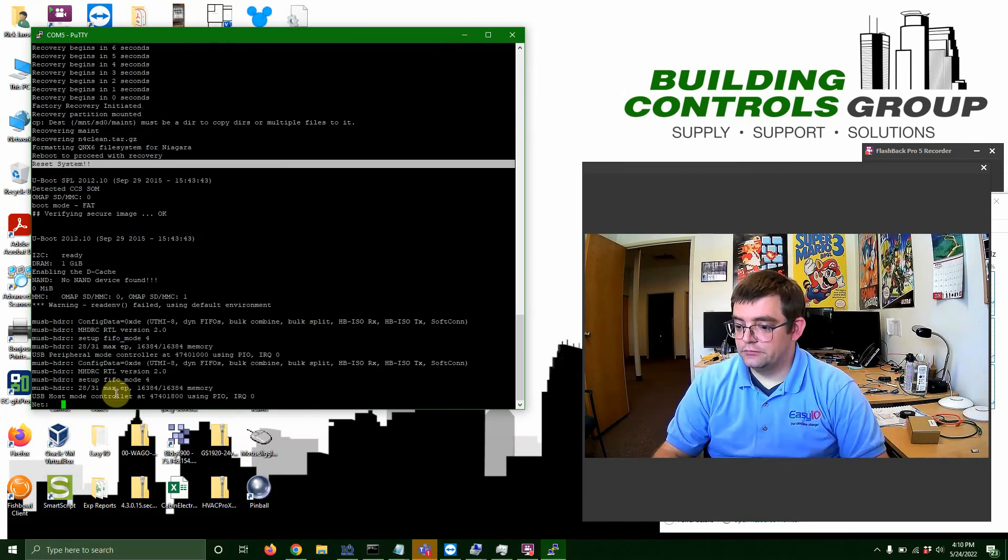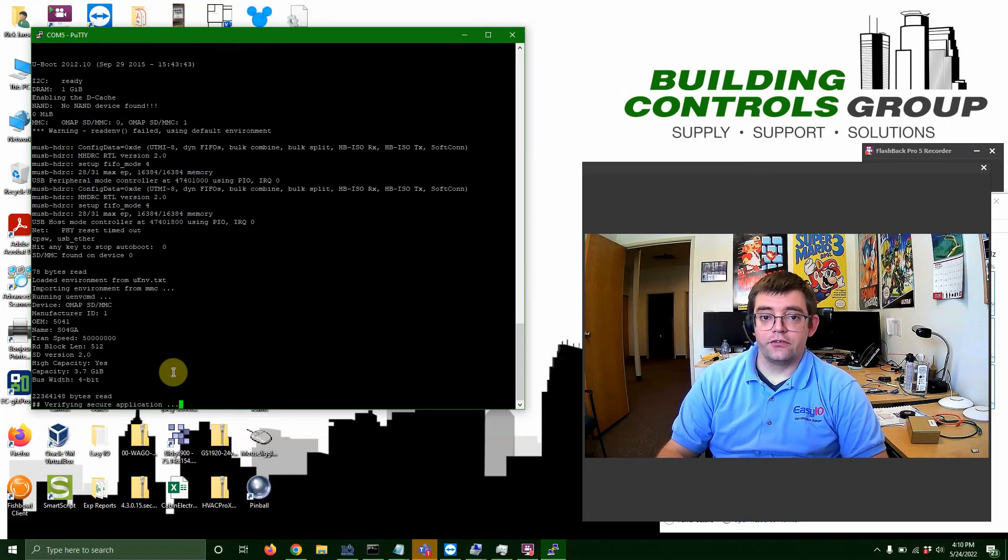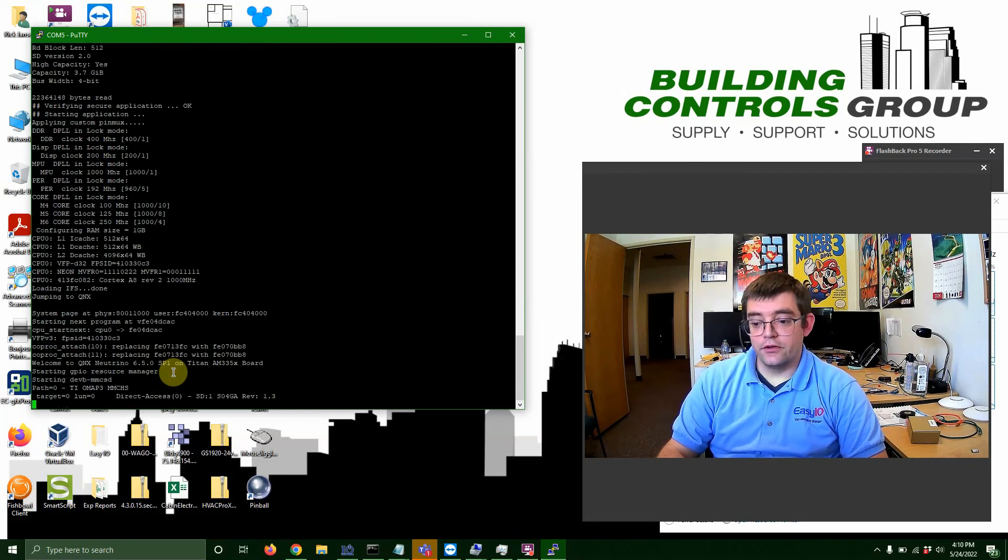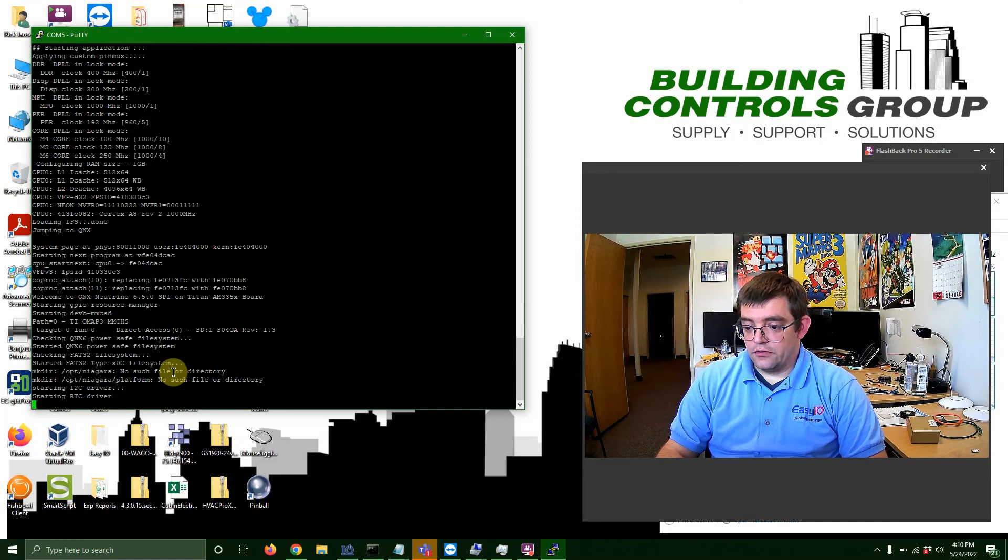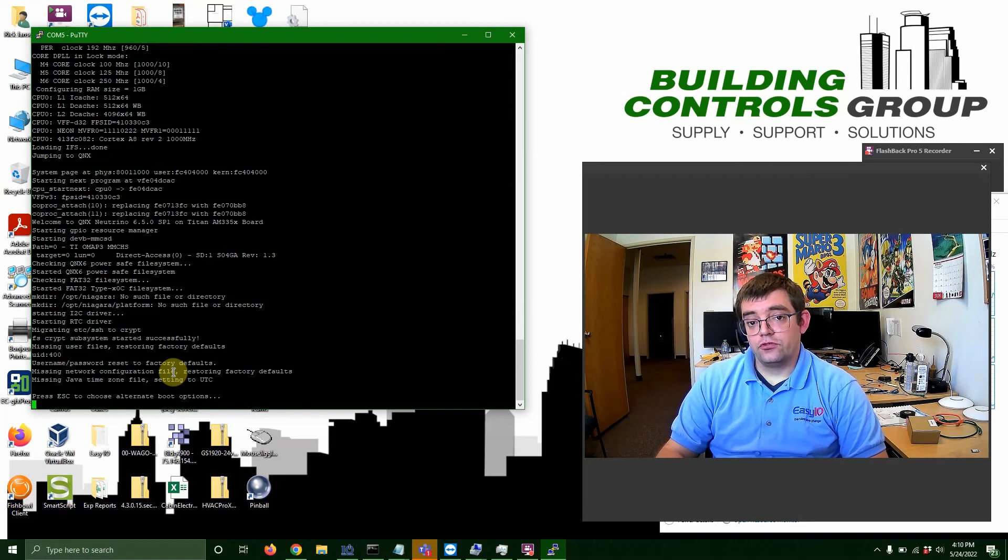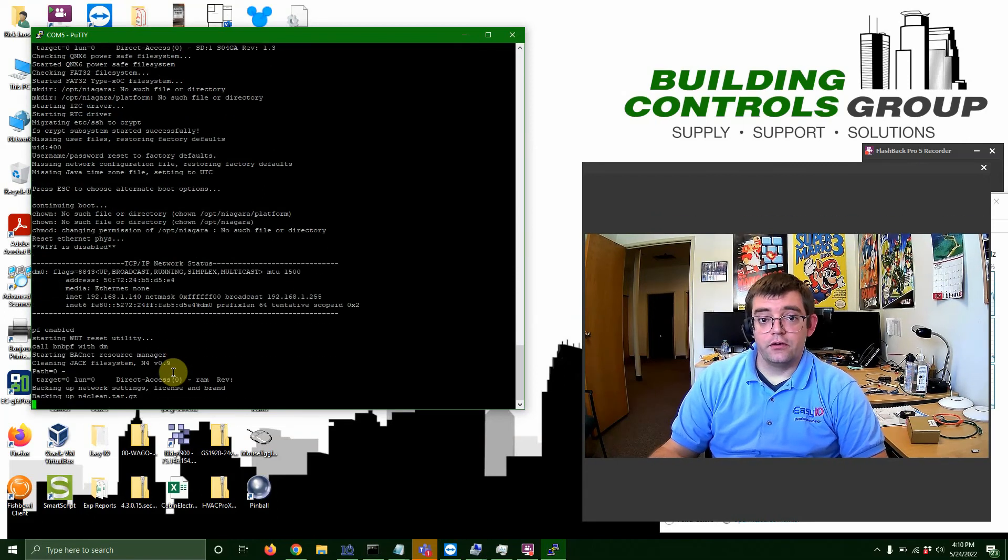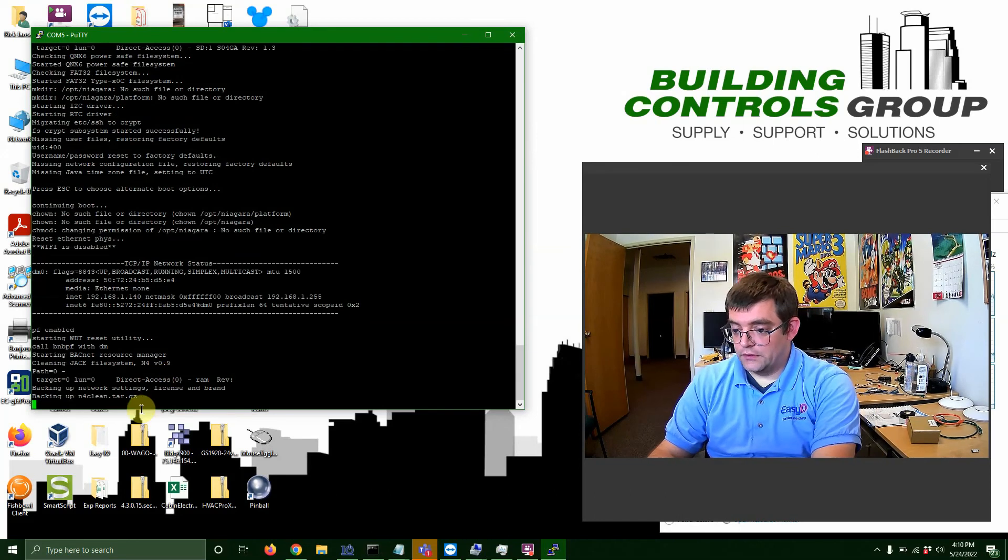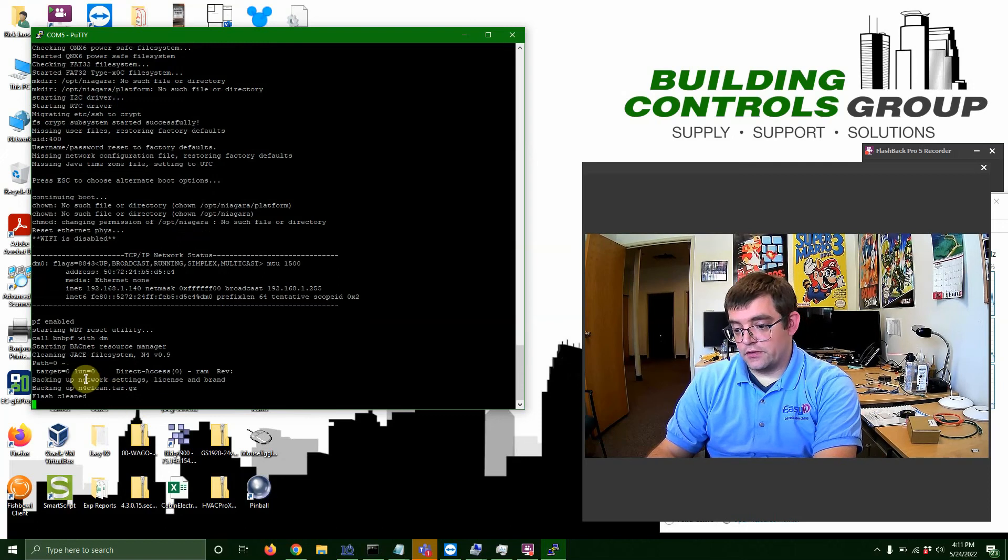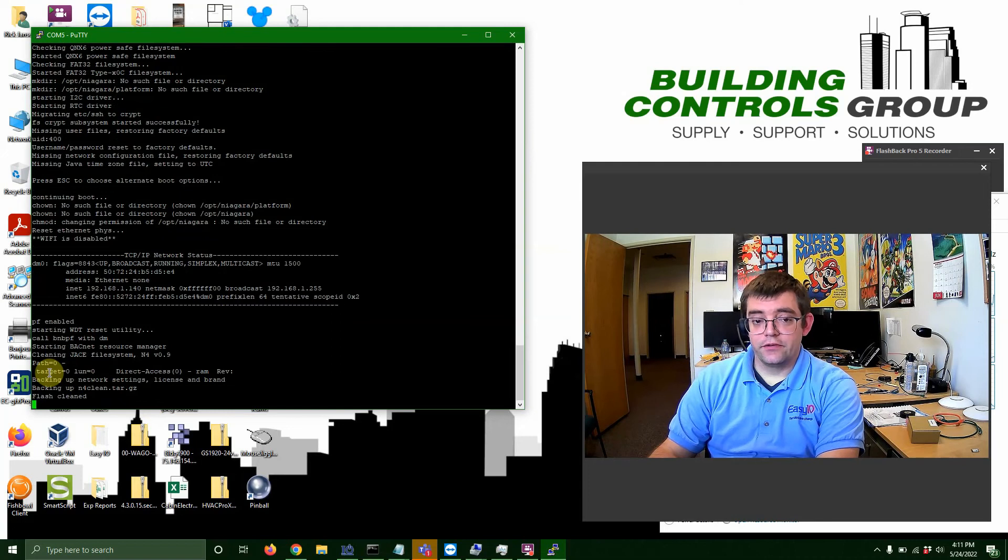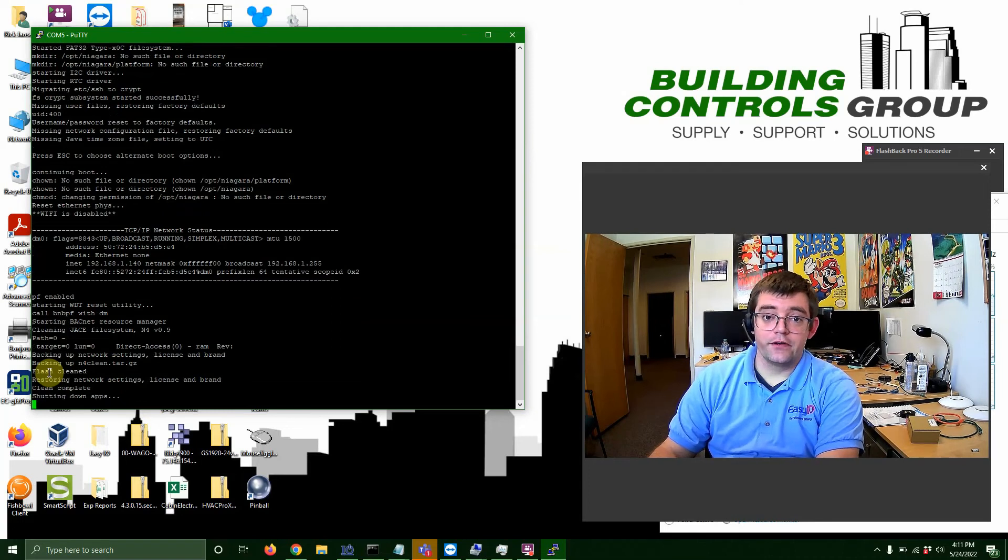So I'm unplugging the Jace and I'm plugging it back in. So now at this point, it's going to go through the cleaning process, install that new clean distribution, and we'll just wipe this thing clean. So at a certain point, basically it will start up the Niagara service and everything so you can get back in through Workbench and recommission your Jace and put your station back on or whatever is you're intending on doing. And I will let you know when we get there, because basically this process takes about five, 10 minutes. So definitely one of those things you just got to sit back and relax and maybe get a cup of coffee or something like that.